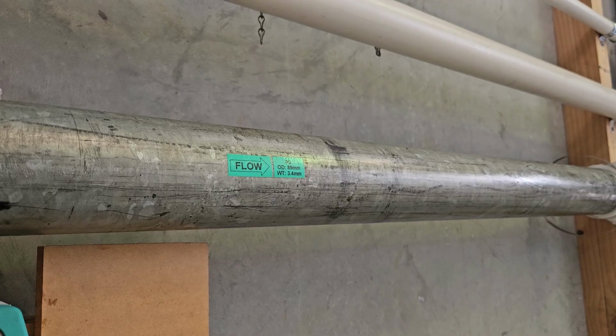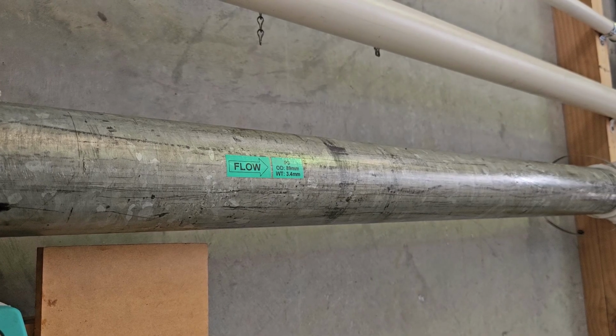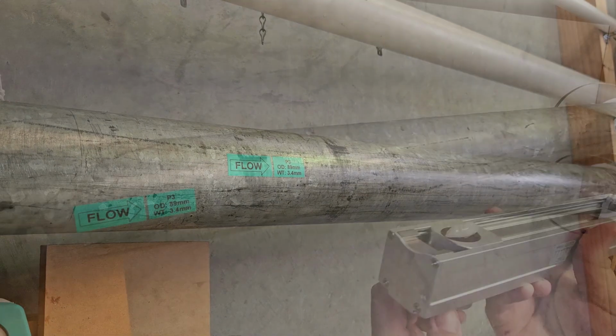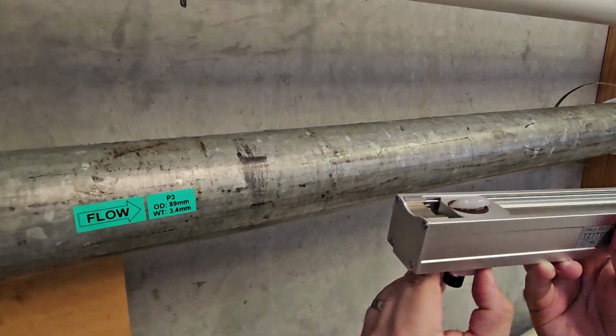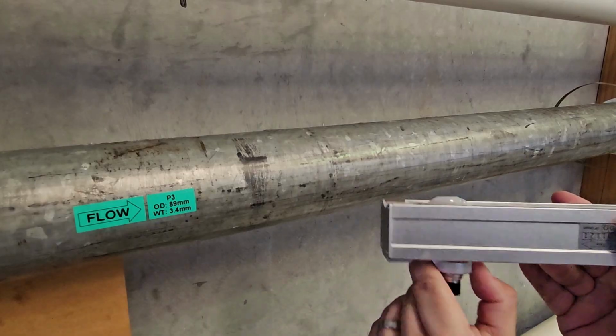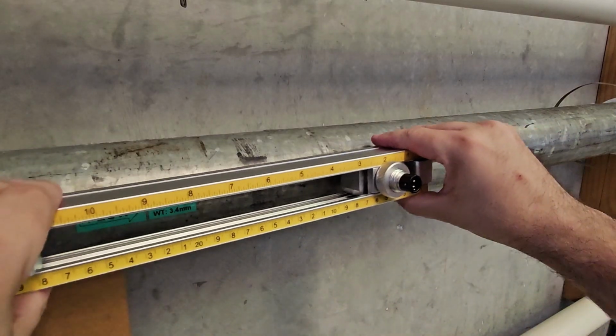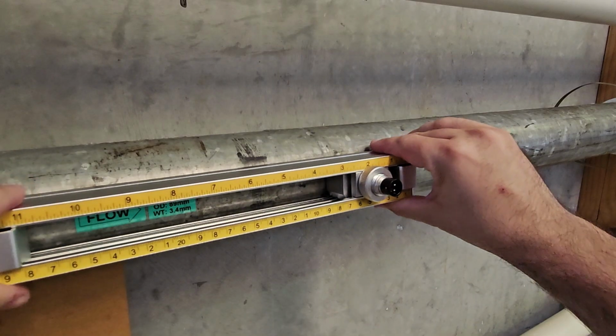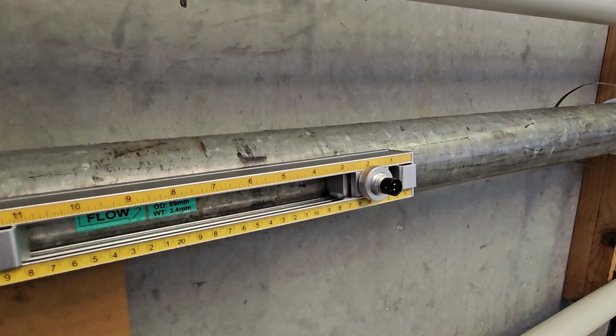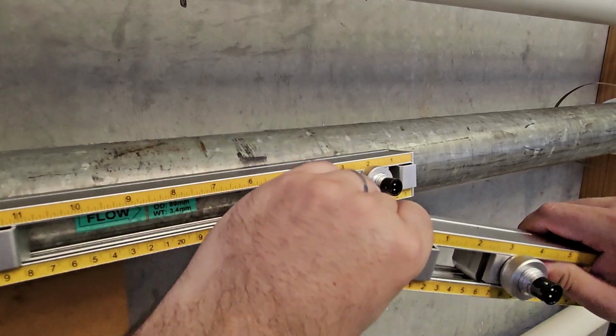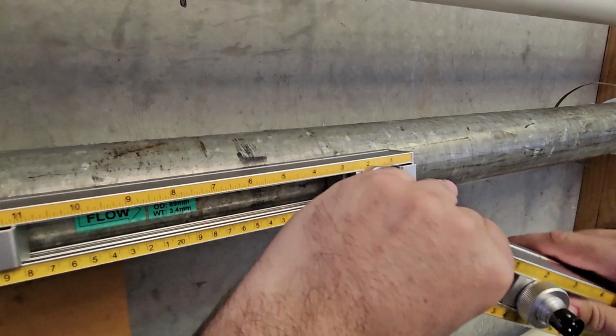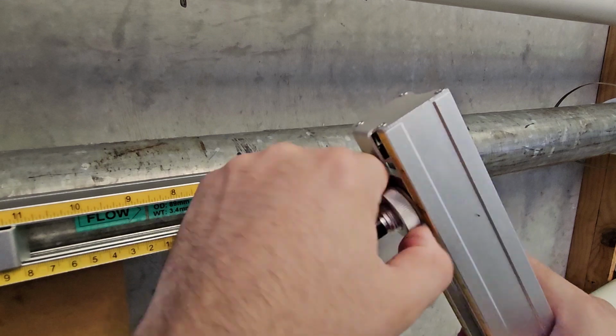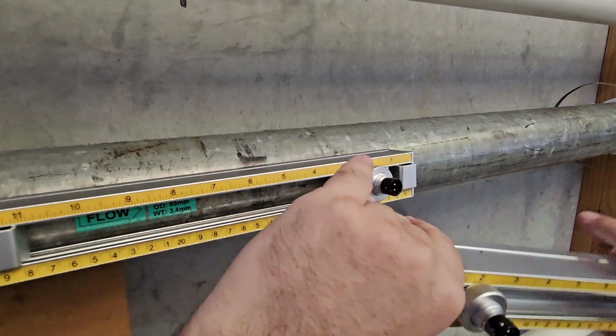In this case we have clean bare metal pipework, but if your pipe is painted, dirty, or rusty, please sand or clean the sensor mounting area. Tighten the adjustment knob to pull the sensor away from the pipe, then place the frame on the side of the pipe. Avoid placing sensors on the top or bottom of the pipe to avoid sediment in the bottom of the pipe or air bubbles in the top. Then gap the downstream sensor, in this case at 3 cm to make a total of 5.77 cm and place it on the pipe too.